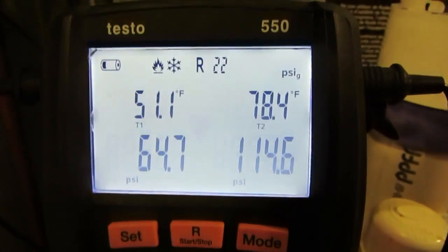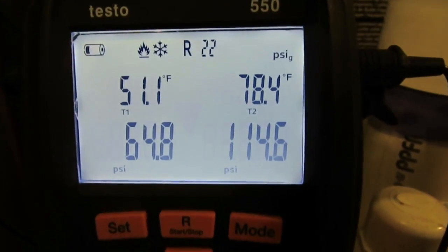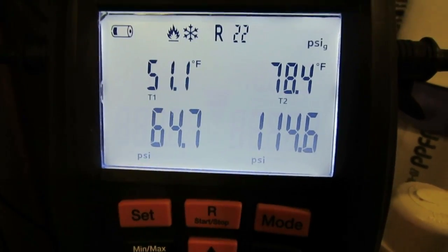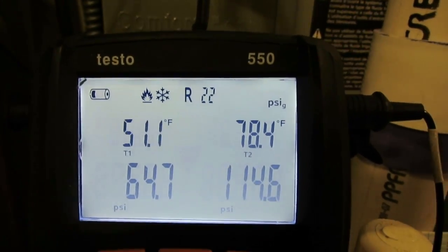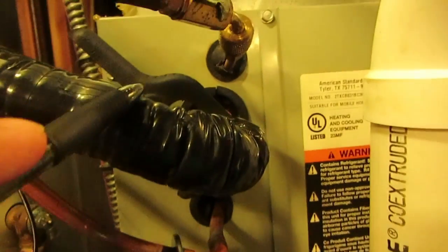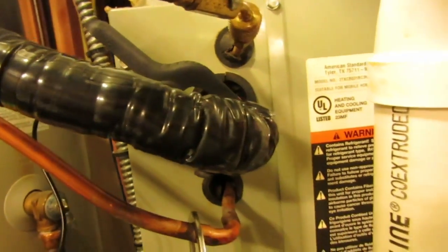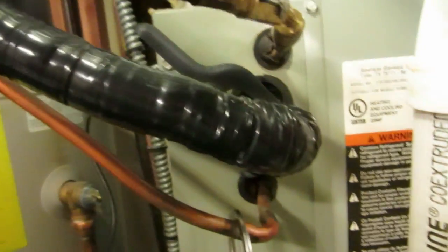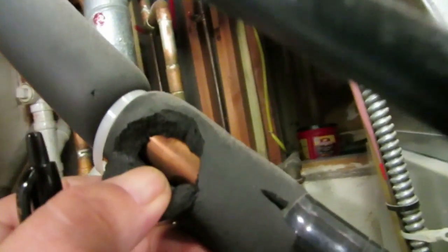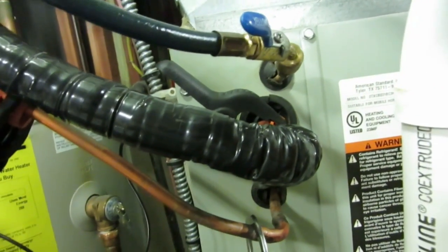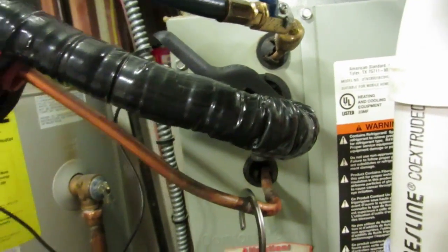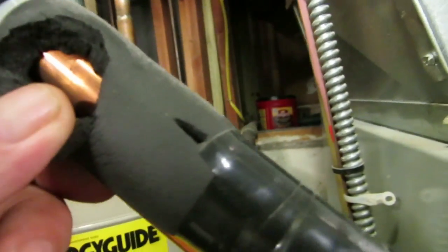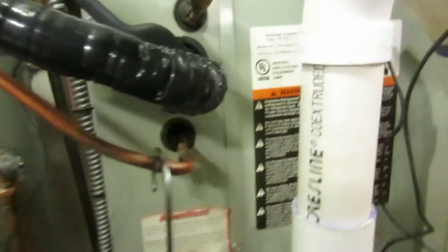I'm not super technical here, so please forgive me if I might word something wrong. I'm not doing it intentionally. But basically this would have something to do with what they call friction loss or pressure loss. That's going to be due to my refrigerant lines here, and I have 90s in my refrigerant lines that could cause friction loss. If you didn't have insulation on your lines, that could cause it. Basically I'm running about 55 foot of line set here. That has a lot to do with it. I'm actually in a conditioned space here. You might have one that's running in an attic and might have got the insulation ripped off of it. That has a lot to do with it.